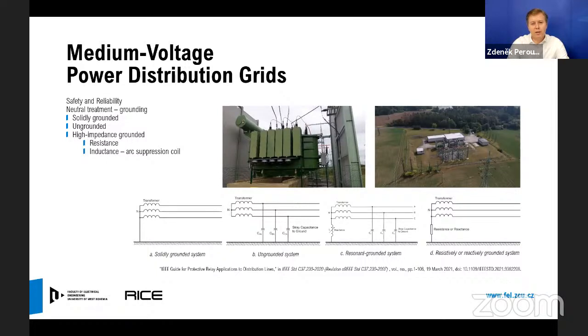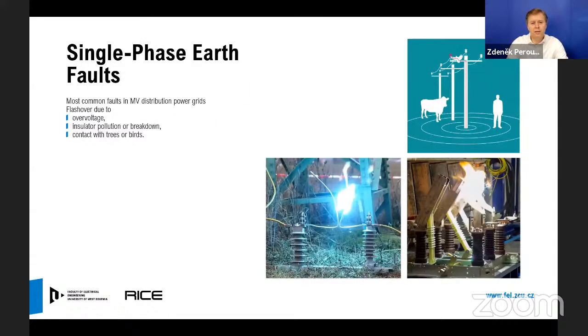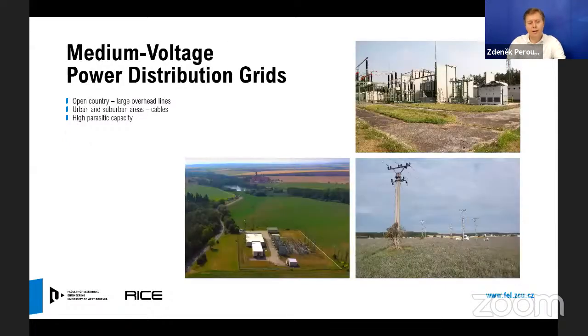I will concentrate on either isolated or high impedance grounded medium voltage power distribution grids, where earth faults are the most common faults due to flashovers, overvoltages, insulator pollution, breakdown, and contact with trees or birds. These phenomena are very well known. Earth faults play a very important role regarding the reliability and safety of the power distribution grid. There is also a new phenomenon, closely related to the increasing parasitic capacity of the grids, specifically in large overhead lines and in urban and suburban areas operating cable grids. That's one of the problems which power distributors are facing at present.